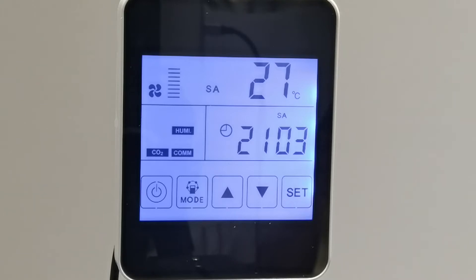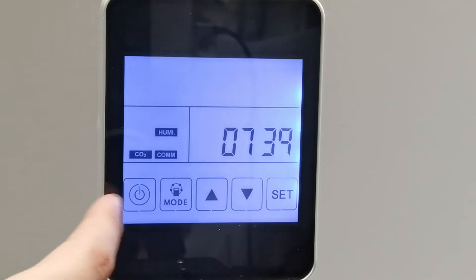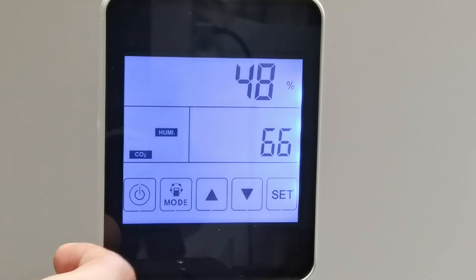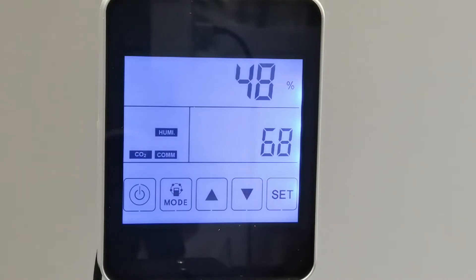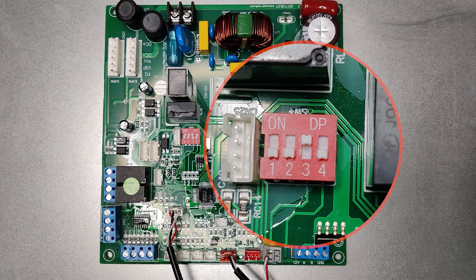When setting the humidity, we can adjust it by pressing the up and down button. The setting range is 45% to 90%. Please remember there is a DIP switch SW423 on the PCB board. It should be turned to ON to make sure the ventilator is controlled by the temperature and humidity sensor.